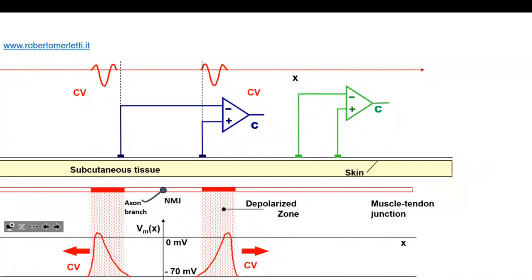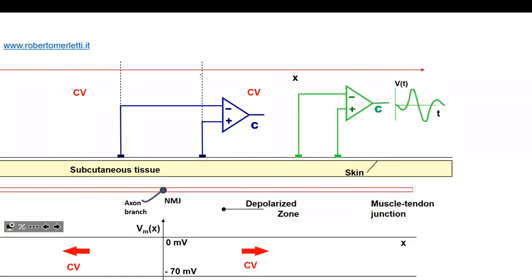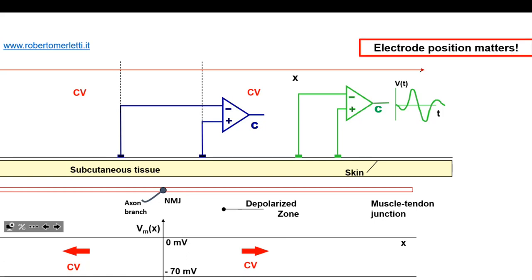If you place two surface electrodes equidistant from the neuromuscular junction, you get zero signal despite electrical activity, because the signals going to the right and to the left cancel each other. But if you place the two electrodes on the same side of the innervation zone, you are able to detect electrical signals. So electrode position matters, and usually with bipolar electrodes you place them on the same side of the innervation zone.